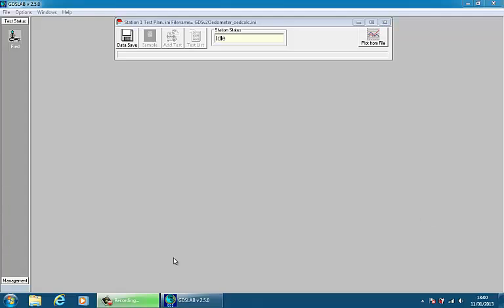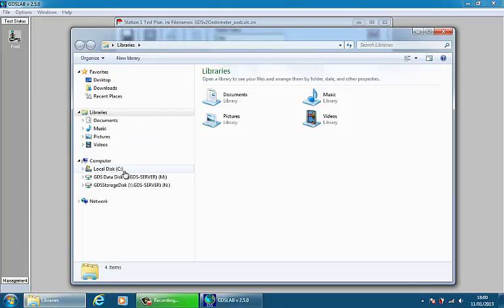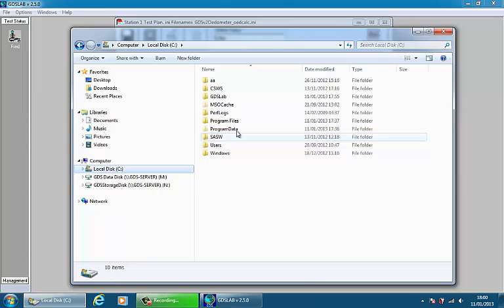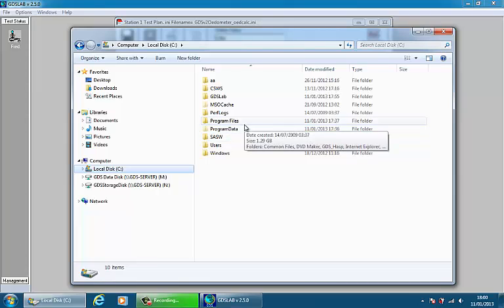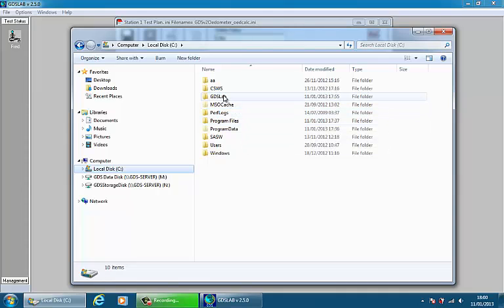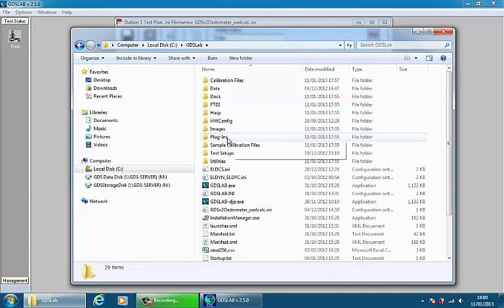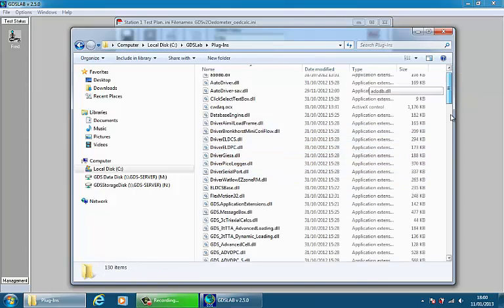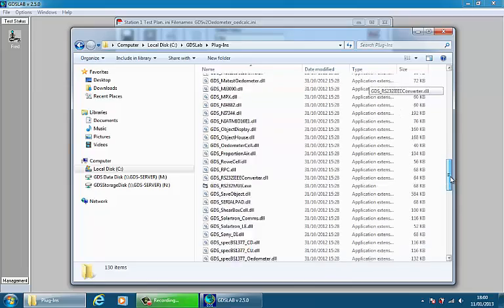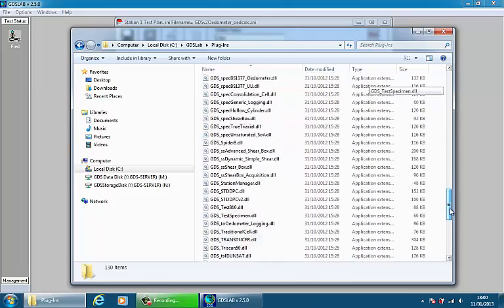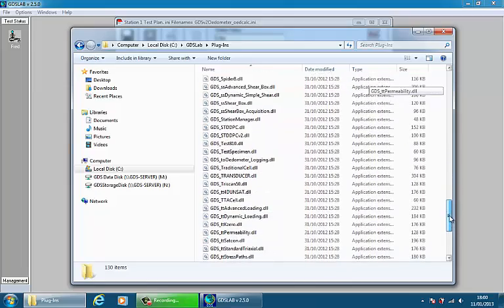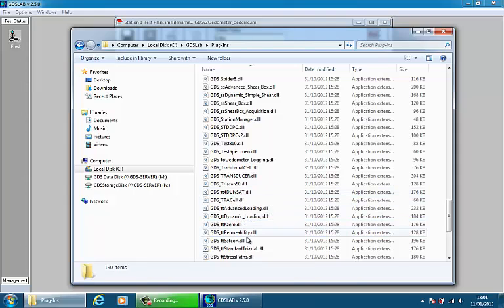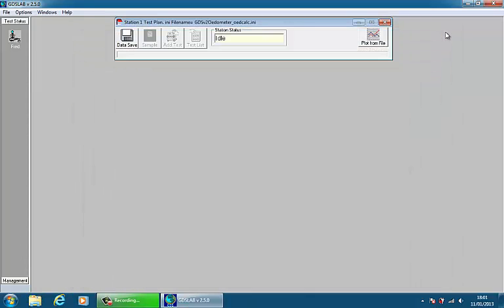I have just started the recording again, because there's one thing I've realized is important in the new version 2.5 that I haven't told you. Test modules are all installed by default, whereas previously in versions prior to 2.5, you would have to install the test modules individually. They are all installed into the plugins directory. For example, if you're familiar with the files, it's normally the one starting TT, perhaps for tri-axial tests. So there's the unsat module, permeability module. They are all installed by default, and only those ones enabled on your HASP dongle are the ones that are actually displayed in your drop-down list. So that makes the installation significantly easier, because it is a one size fits all, and off you go. Okay, thank you.